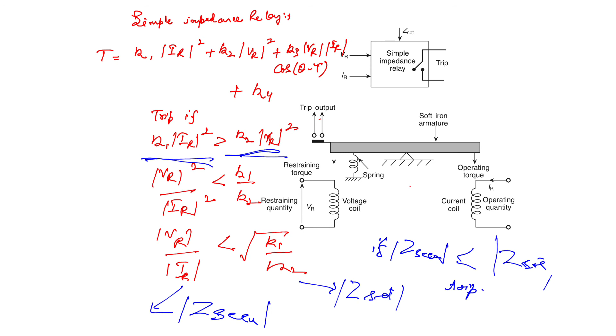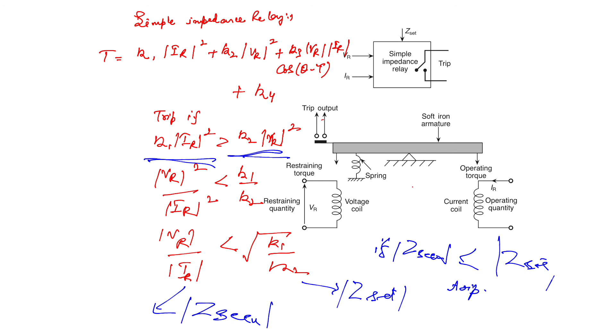So we can say that a simple impedance relay is an overcurrent relay with voltage restraint, because we have the operating torque as this, and this is the restraining torque, which is negative. So it is an overcurrent relay with voltage restraint.